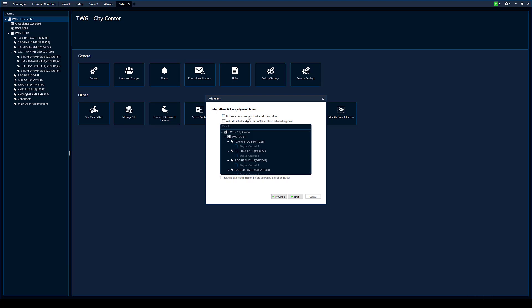So basically you can require a comment when acknowledging the alarm, and you can also have an activated digital output when the alarm is acknowledged, and you can also require a confirmation before firing that output. So say you need to reset a bell or reset a strobe or something, you can do that here.